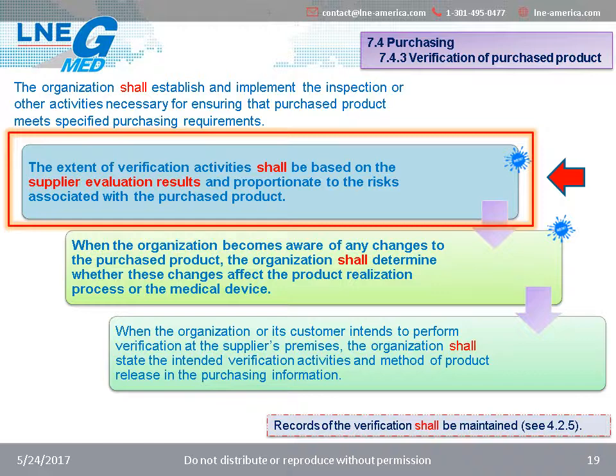And then in section 7.4.3, it is also not specific to supplier control, but to the verification of purchased product. We can find a link to the supplier evaluation in the requirement linked to incoming inspection. The extent of verification activities should be based on the supplier evaluation results and proportionate to the risk associated with the purchased product. This is where organizations may, for example, adjust their incoming inspection sampling plan based on the supplier's performance with past deliveries.